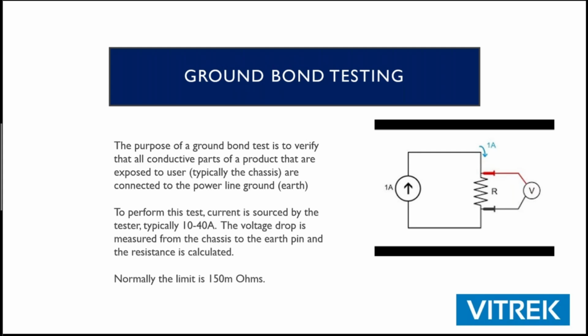For ground bond, you're typically going to be in the 10 to 40 amp range. Normally, your requirement's going to be 150 milliohms or less. Those resistances can be a little bit higher if you're just required to do a continuity test. But either way, it's the same. There's going to be current sourced, and then we're going to measure the voltage drop across your device. Convert that over to ohms, and that is going to be your pass or fail criteria.